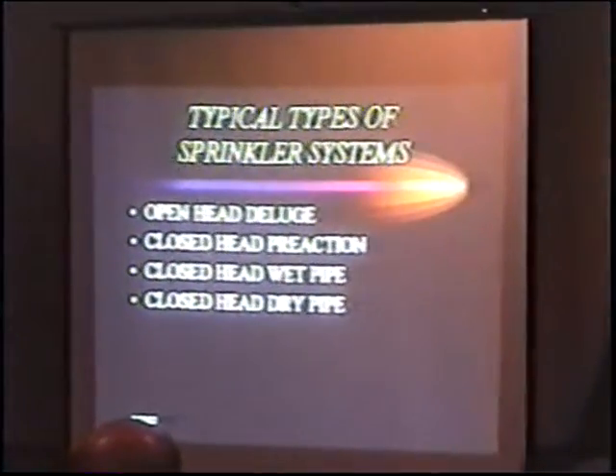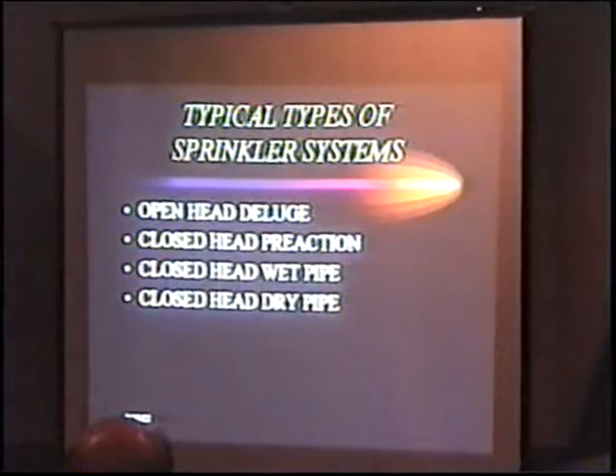Various types of sprinkler systems, you guys are familiar with all that. Open head deluge, probably one of the most common out there. Very common application with AFFF. Closed head pre-action, we're starting to see that a little more often now in airplane hangars, getting away from the deluge systems because of all the false dumps. AFFF solution on the avionics and expensive jet airplanes does not work well. So they're going with the pre-action systems to eliminate that unfortunate incident.